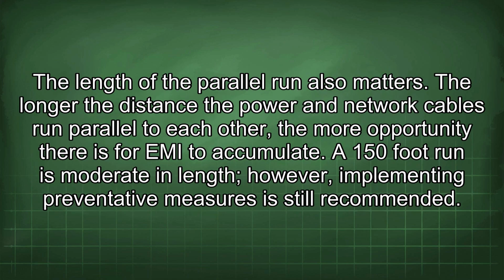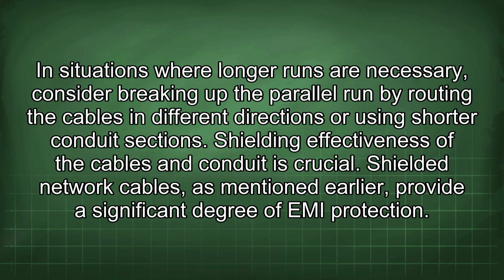The length of the parallel run also matters. The longer the distance the power and network cables run parallel to each other, the more opportunity there is for EMI to accumulate. A 150-foot run is moderate in length, however, implementing preventative measures is still recommended. In situations where longer runs are necessary, consider breaking up the parallel run by routing the cables in different directions or using shorter conduit sections.